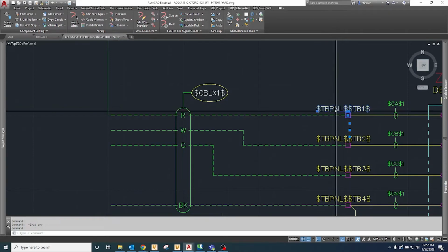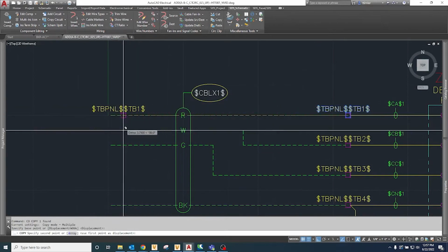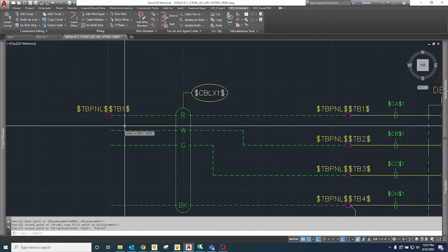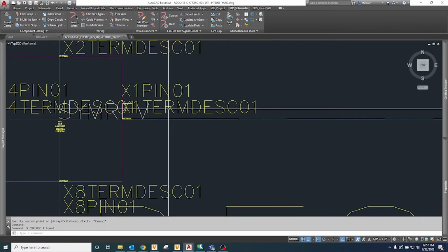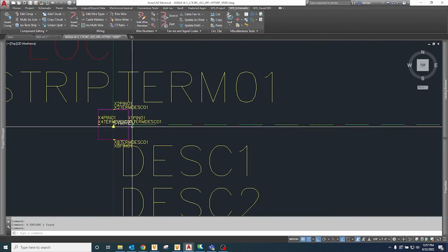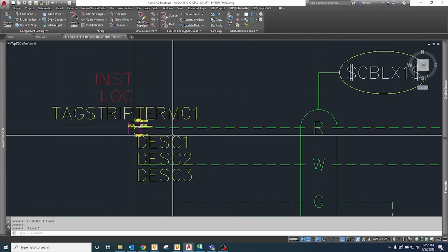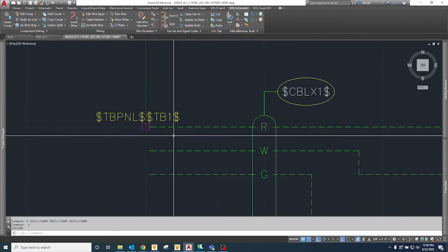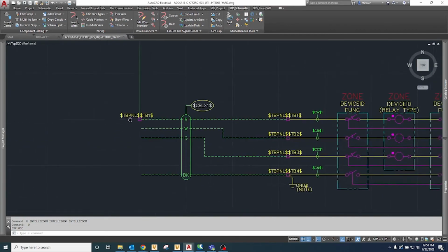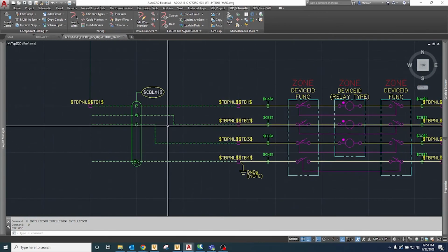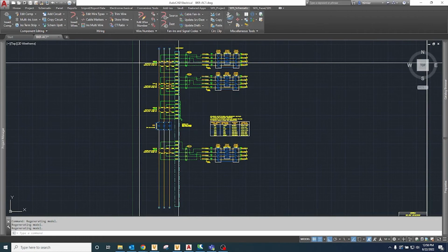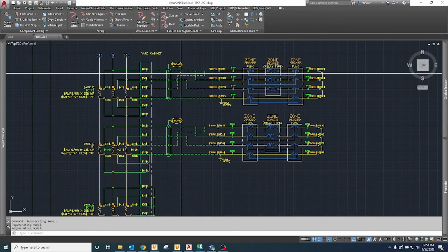If I open up an example to explain the relationship between the circuit insertion point and the target symbol used in Add Circuit, the insertion point for the circuit is offset from the drawing origin point by the same distance as the associated symbol's insertion point. So you can see the terminal's connection point attribute is going to line up with the cable, and that's how much you have to offset the distances for the circuits so they snap in place. Because this happens, AutoCAD Electrical can see the connection in the Project Scratch database after you use the Add Circuit tool. I can quickly add schematic cable fan-ins using the SDS Add Circuit tool as well.